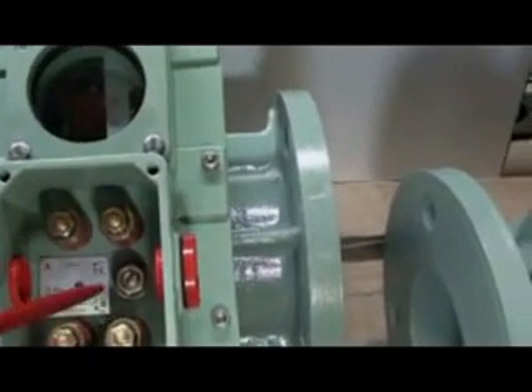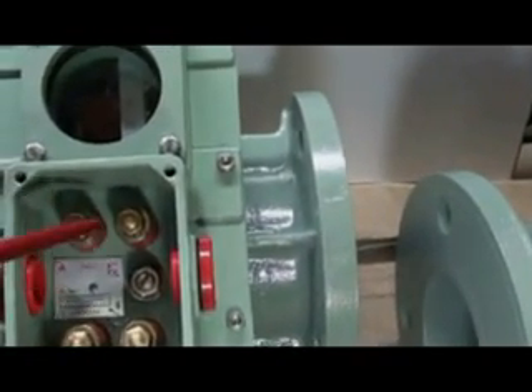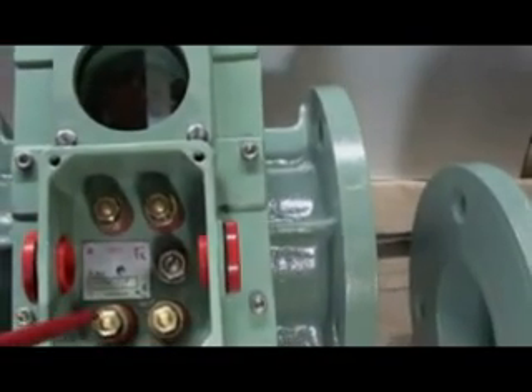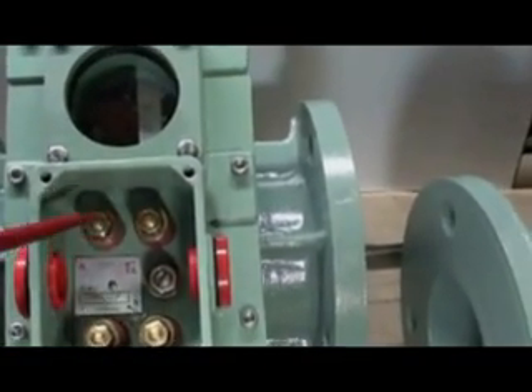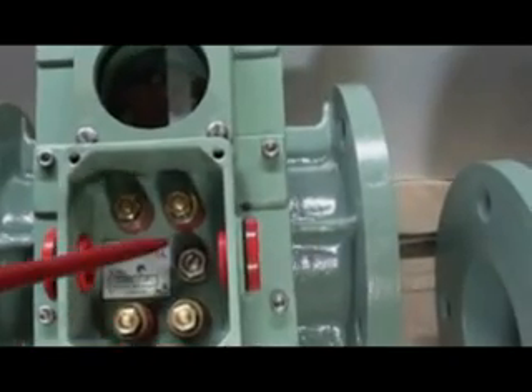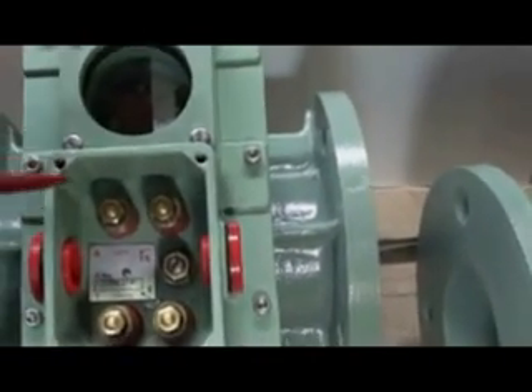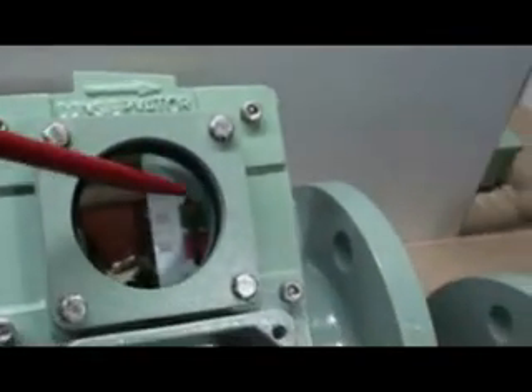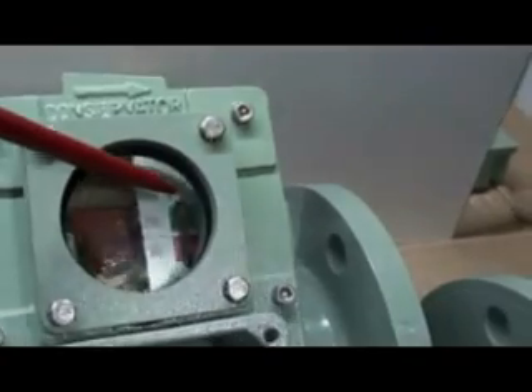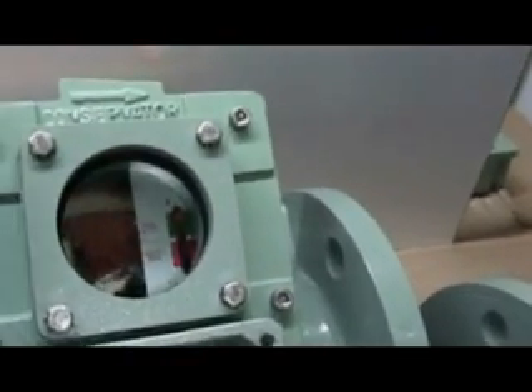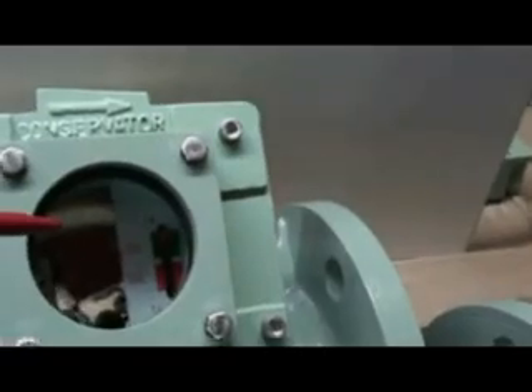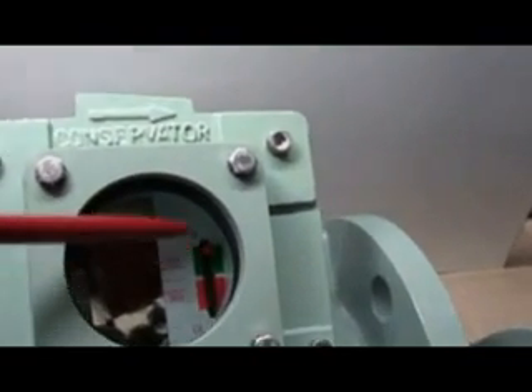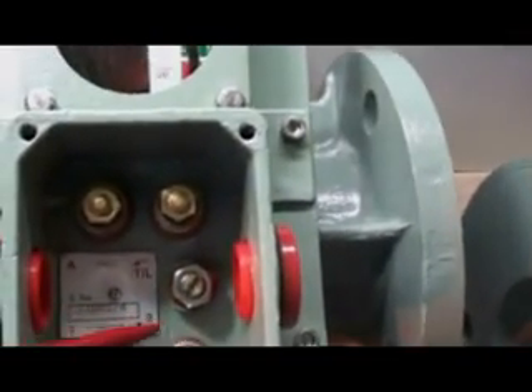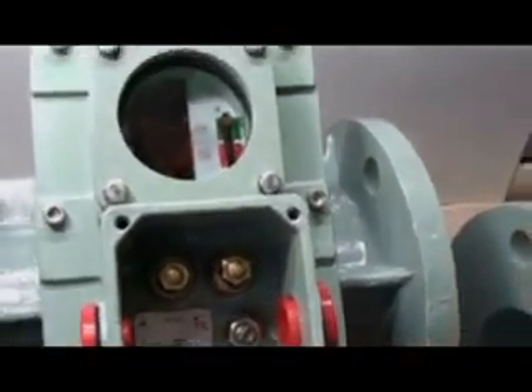In transport lock position, alarm and trip both will show continuity. In service position, alarm and trip both will not show continuity. We can test the Buchholz relay without applying any compressed air. There is a red color pointer located at S position. When the key lock slot moves to TL position, the red pointer moves to TL position. In TL position, it shows continuity in both alarm and trip circuits. In this way, we can check the function of Buchholz relay at site.